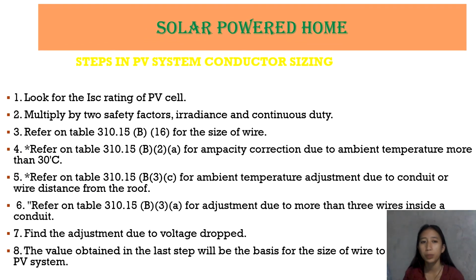Okay, so let's proceed to the steps in PV system conductor sizing. The first step is to look for the ISC rating of the PV cell. Next is multiply by 2 safety factors: irradiance and continuous duty. Third, refer to table 310.15 B16 for the size of wires. And then refer also to table 310.15 B2A, para malaman natin yung ampacity correction due to ambient temperature more than 30 degrees Celsius.